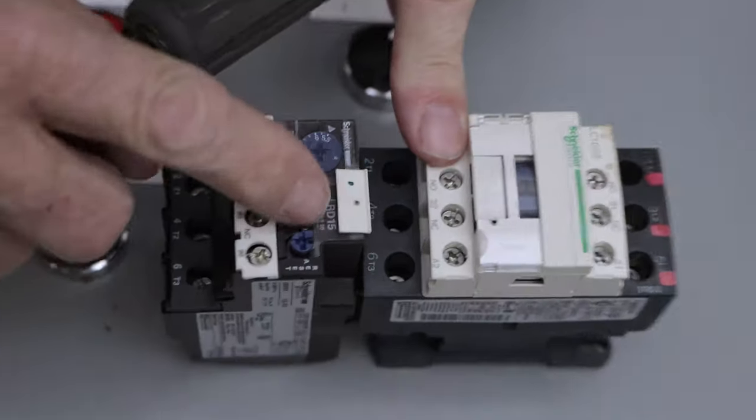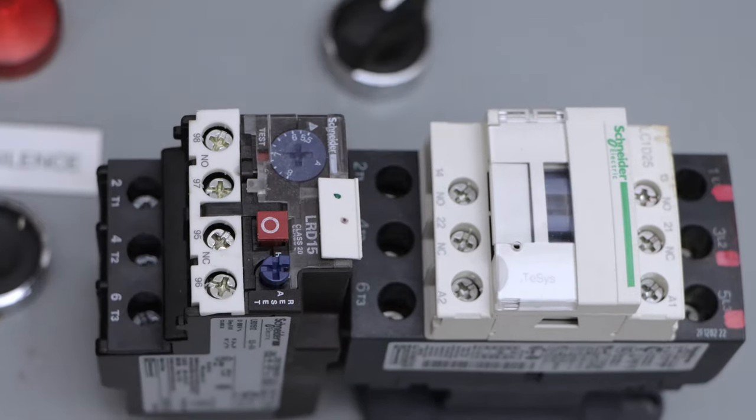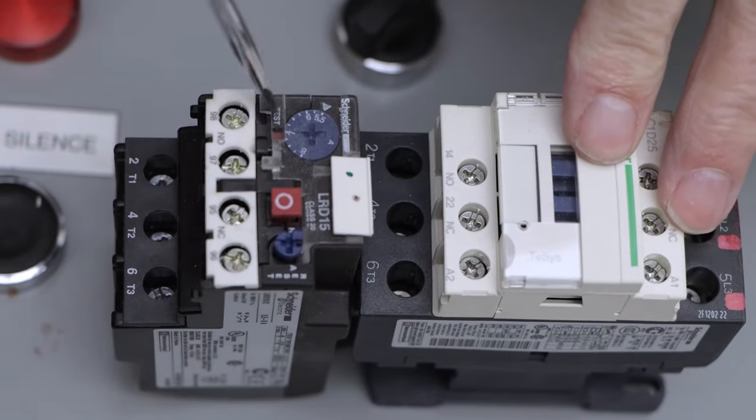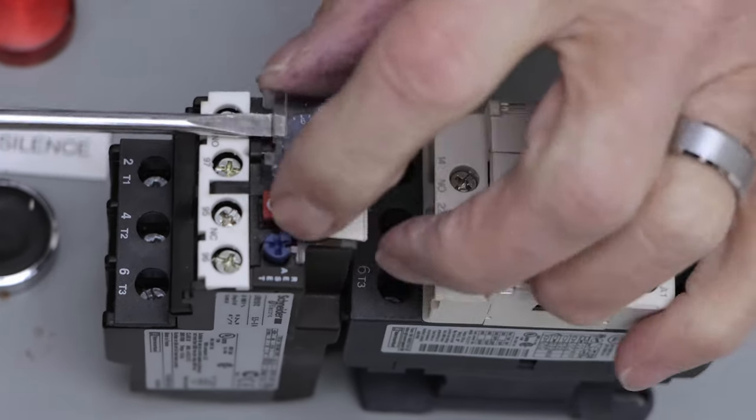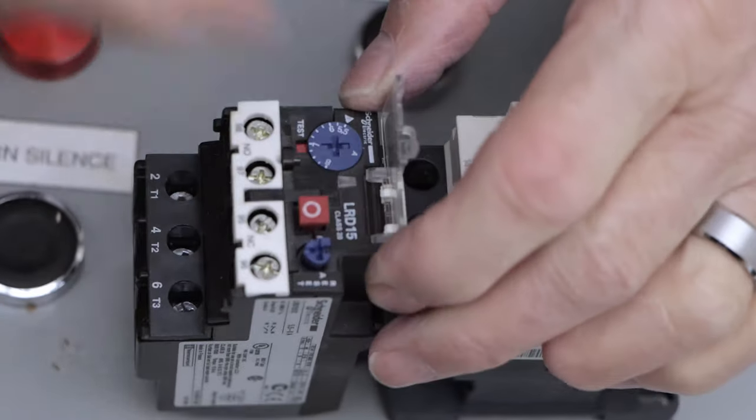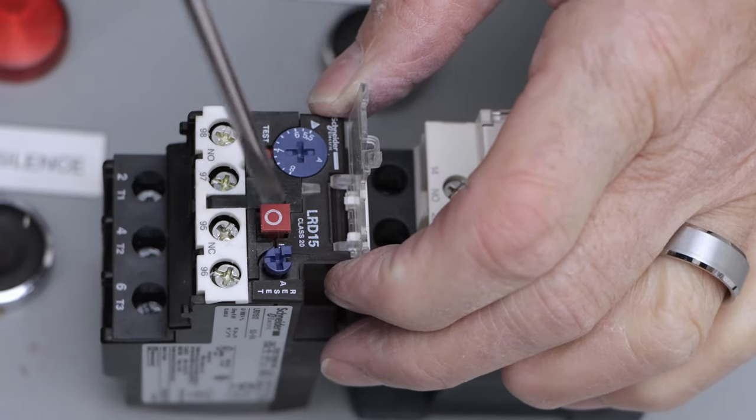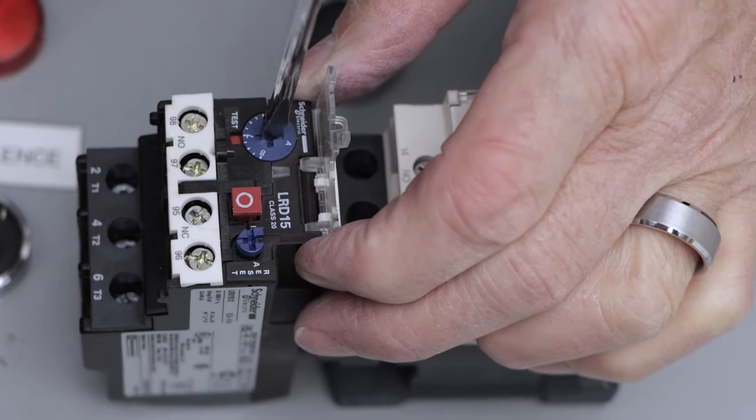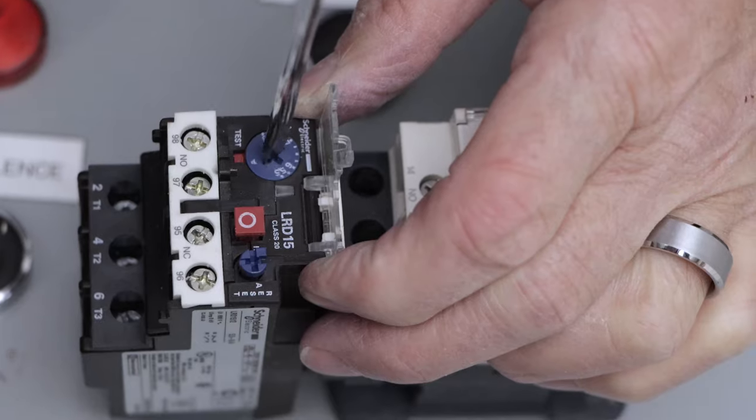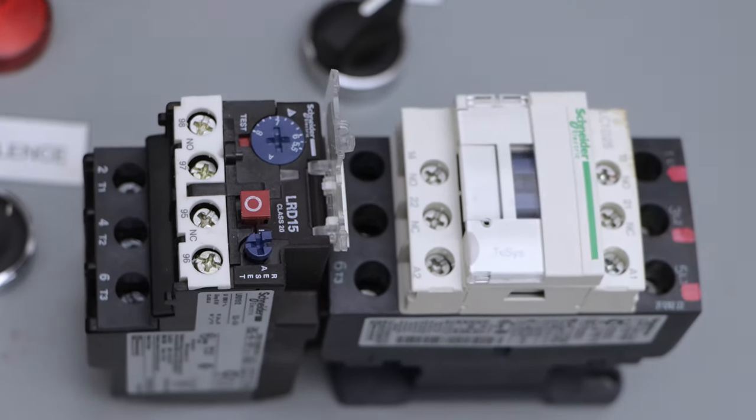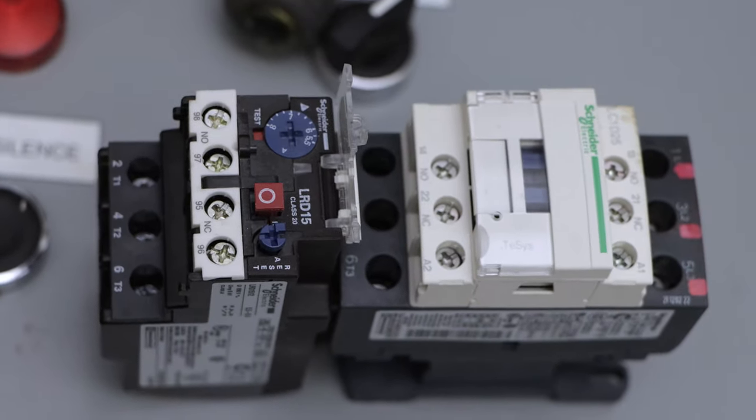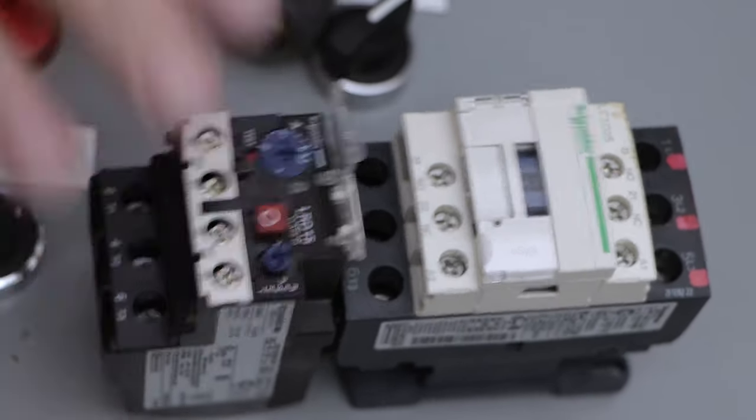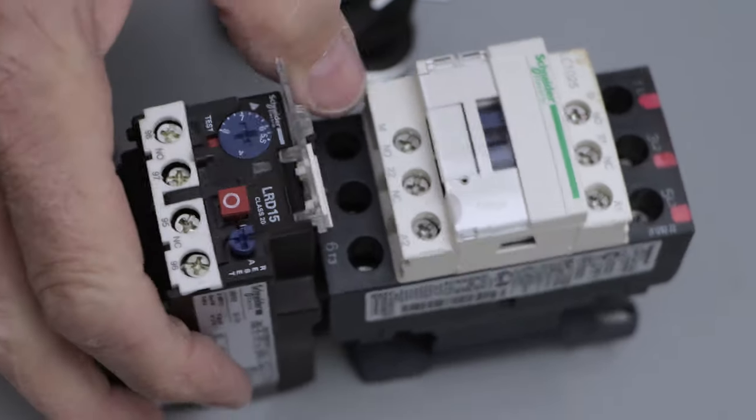This is a reset button right here. We've got an overload setting, so unlike the NEMA starter, we can actually dial in the amount of overload protection we want underneath this window. So this is an LRD15. It has a certain range of current that it can be set from, and we can dial that in to any amount we want. So let's say, for instance, we have a motor that draws 10 amps. So we can dial this into 10 amps, and that immediately sets our overloads for 10 amps of overload.